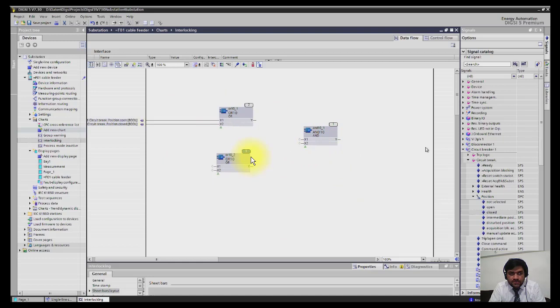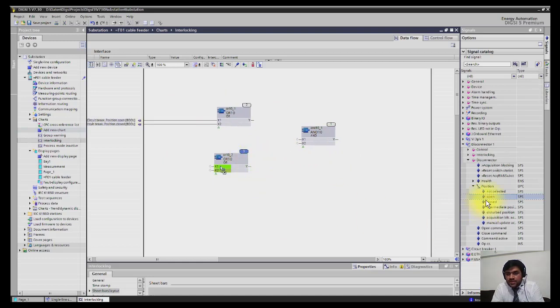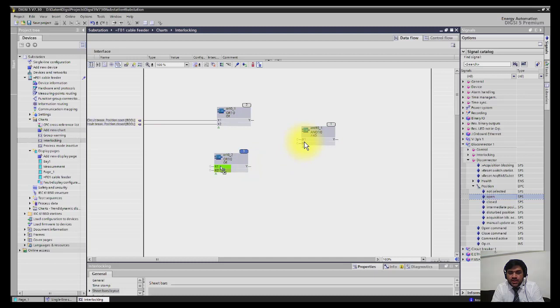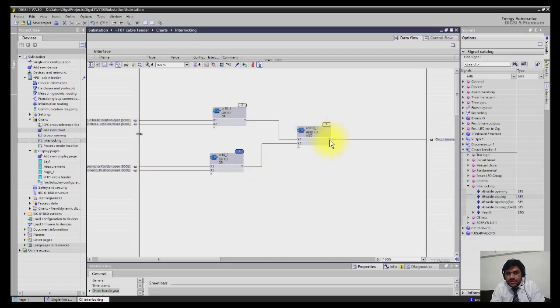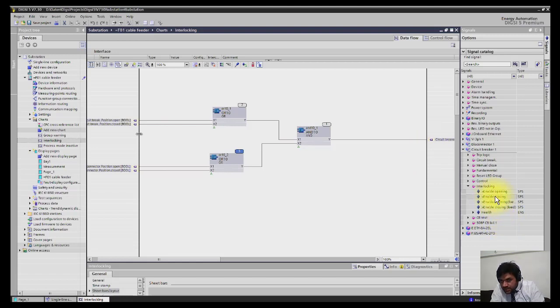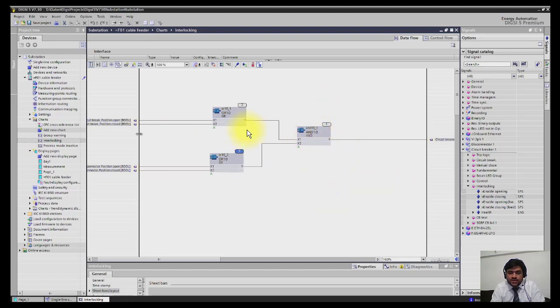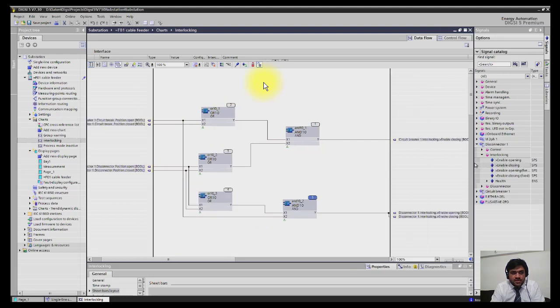In the same way I will now select open status of the isolator disconnector and drop it to X1, and then close status. I have to connect these two wires to X1 and X2. Finally, I will connect the output of this gate by dragging enable closing and dropping it to Y. Now we should have a very clear status of isolator and breaker to operate the breaker itself. This is how you are defining the logics.